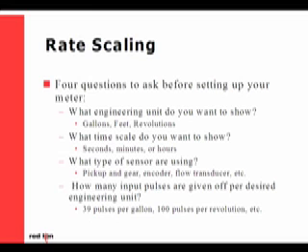Before I explain the equation used to determine rate scaling, let's ask some questions pertinent to our application. First, we need to know what engineering unit we want to show, whether it is in gallons, feet, revolutions, or another engineering unit. Next, we need to know what time scale we want to show — some examples are per second, per minute, or per hour. Next, we should know what sensor we are using and how many pulses are given off per engineering unit. If we were measuring gallons per minute, we would need to know how many pulses come off of our sensor per gallon.